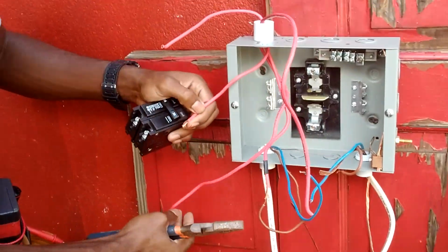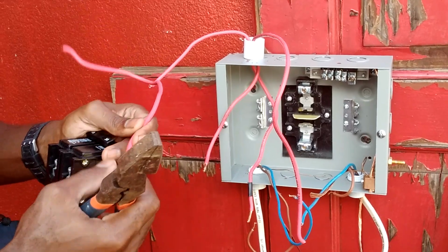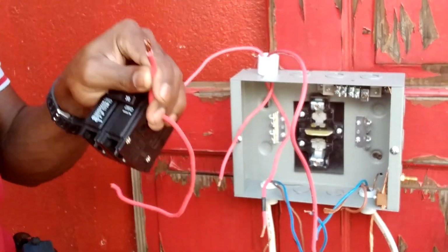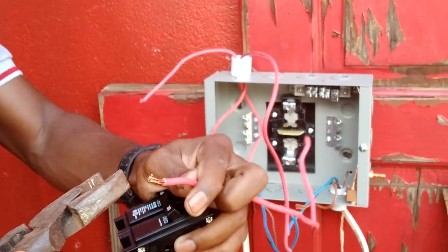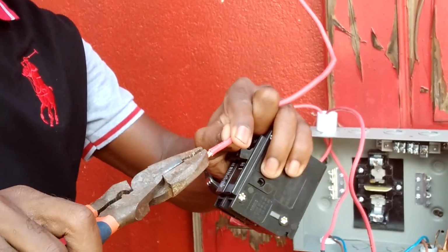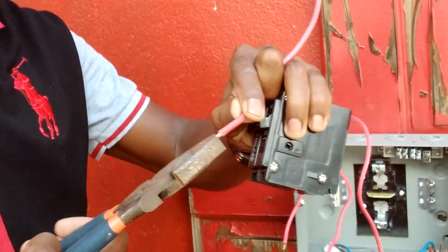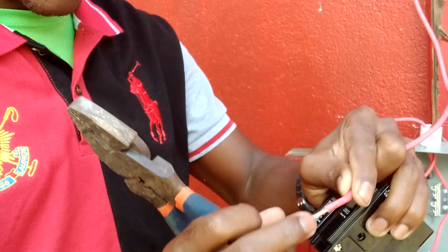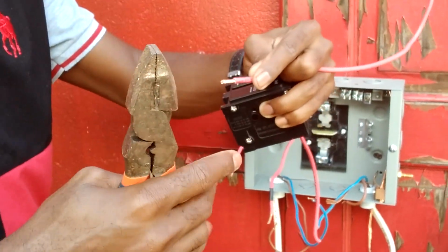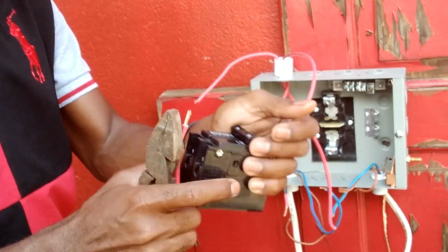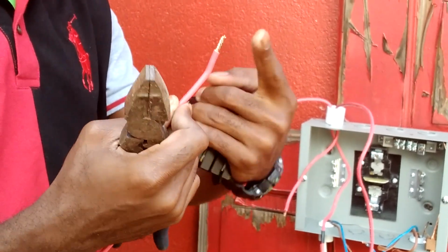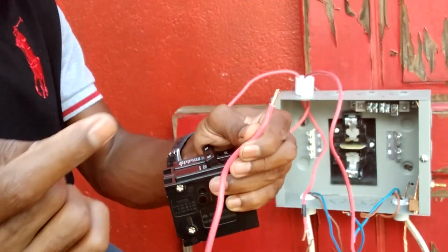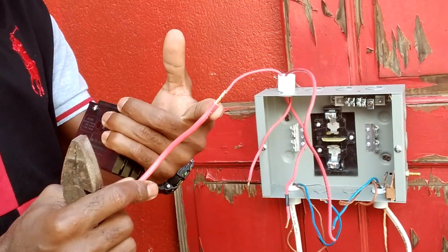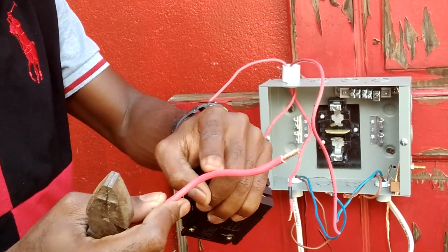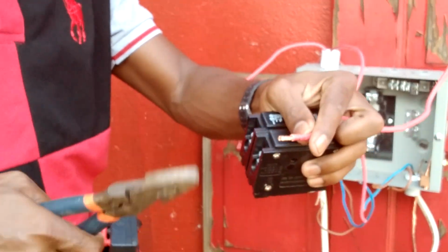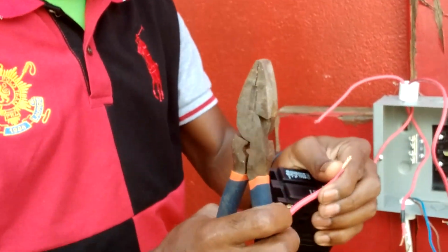Since this is a stranded wire, let me take it out — it keeps falling out. Because it's stranded, I have to give it a little twist, what we call stranding. This increases the current carrying capacity of the wire, because if the strands are separated when connected into a terminal, the electricity will only feed through some of the strands while others are left out. That decreases the current carrying capacity, and the wire can start to burn or overheat. So you have to ensure you twist all the wires together and get them in there nice and perfectly.